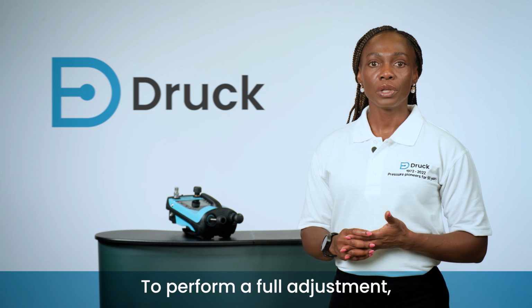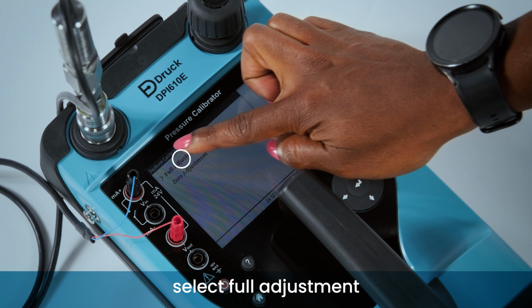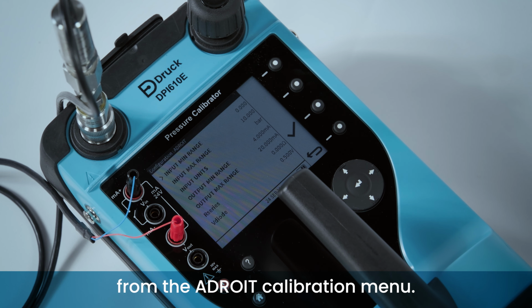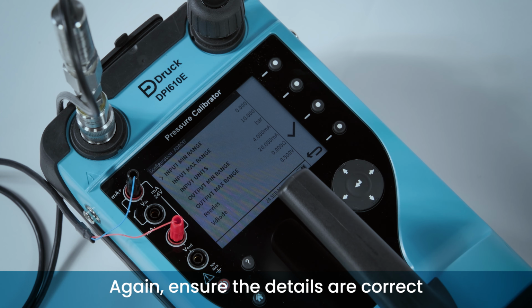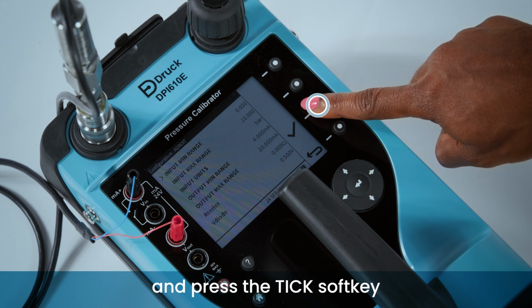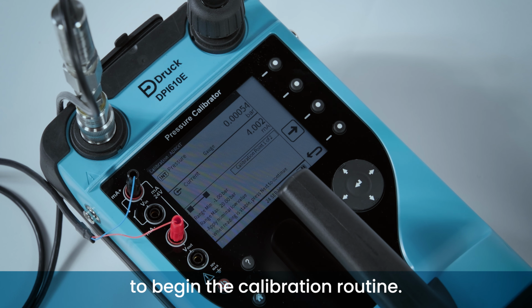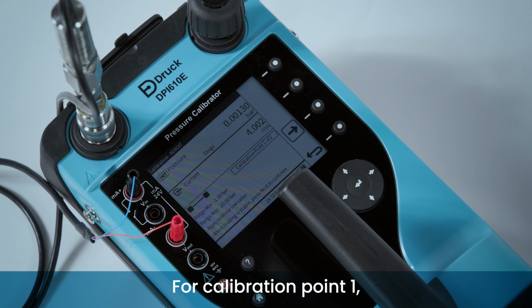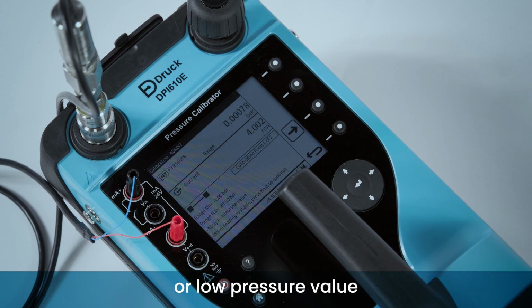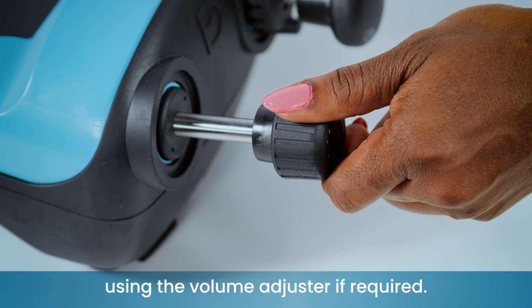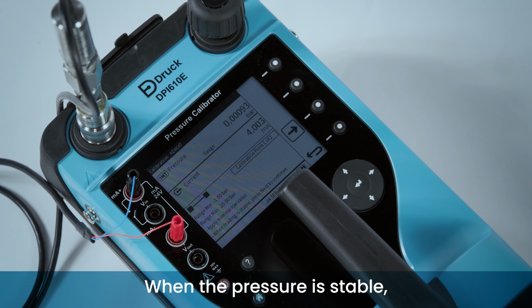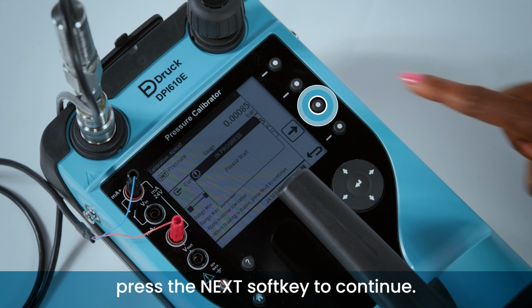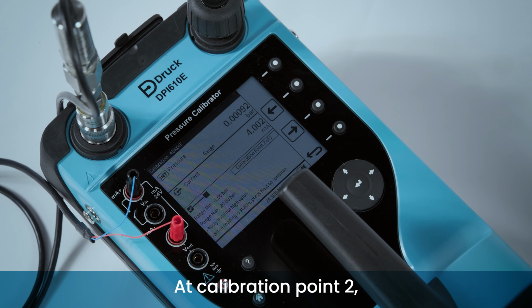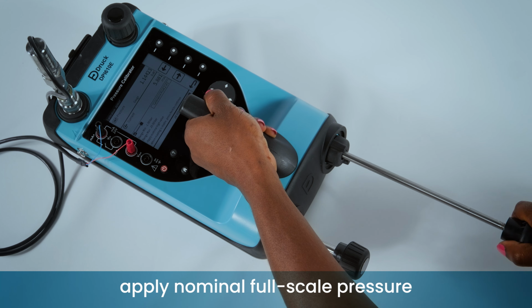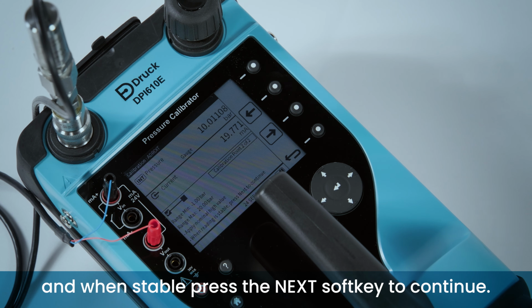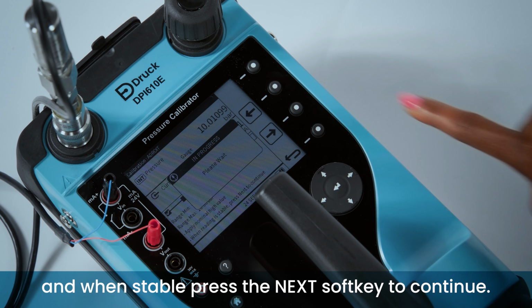To perform a full adjustment, select Full Adjustment from the ADROIT calibration menu. Again, ensure the details are correct and press the tick soft key to begin the calibration routine. For calibration point 1, we apply nominal zero or low pressure value using the volume adjuster if required. When the pressure is stable, press the next soft key to continue. At calibration point 2, apply nominal full scale pressure, and when stable, press the next soft key to continue.